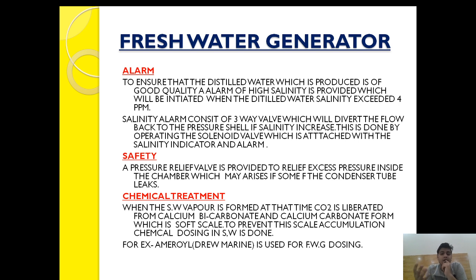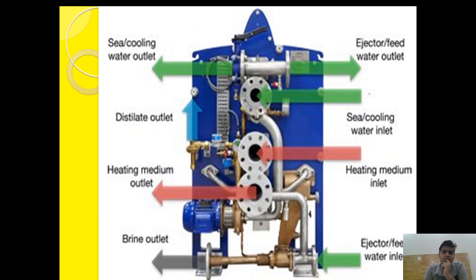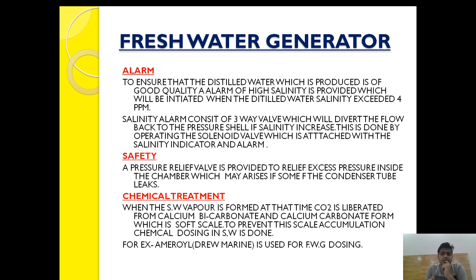What are the safeties provided in the fresh water generator? A pressure relief valve is provided to relieve excess pressure inside the chamber, which may arise if some of the condenser tubes leak. If there is a major leakage, even though the brine ejector is removing excess sea water, the whole chamber may get filled and build up excess pressure. To prevent this, a relief valve is provided on top of the pressure chamber to release excess pressure. That is the safety provided in a fresh water generator.